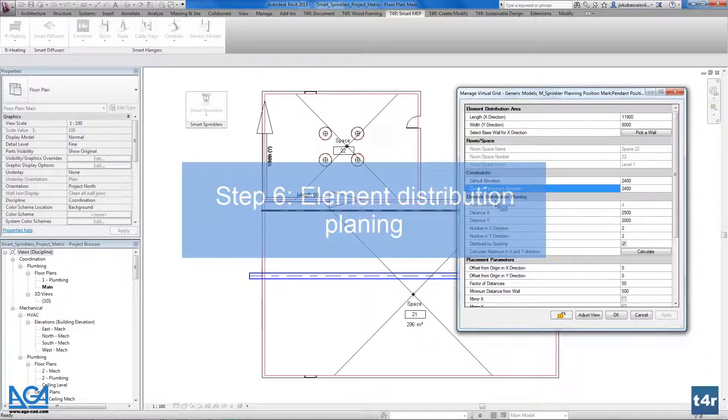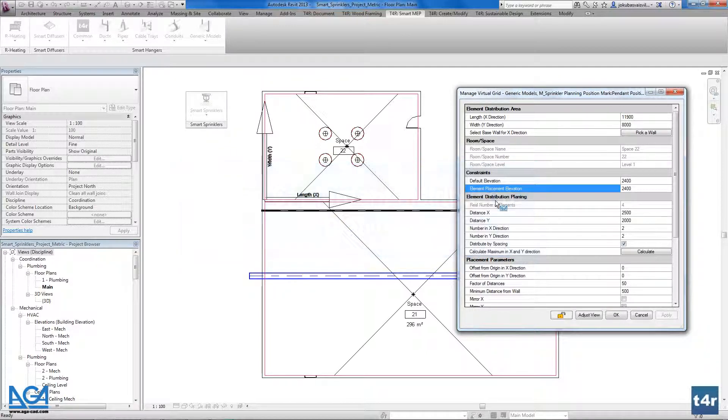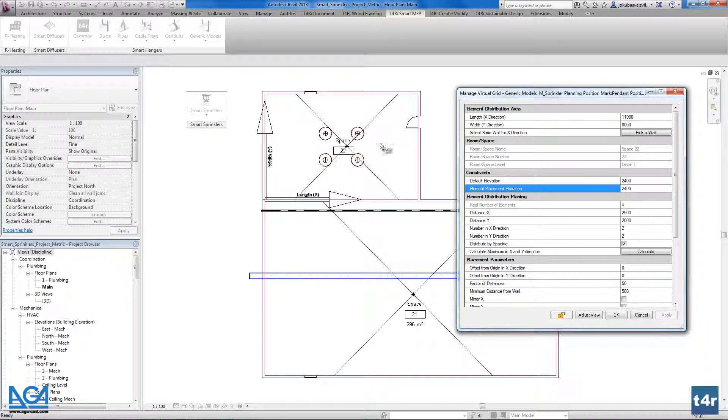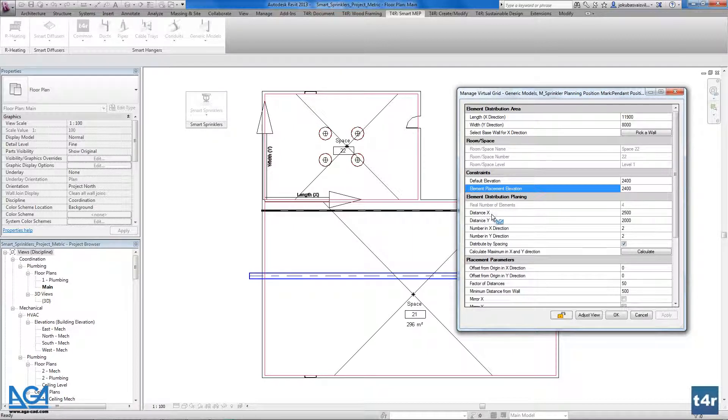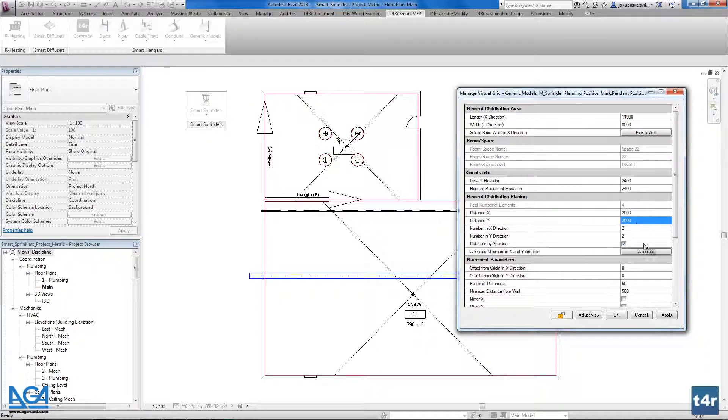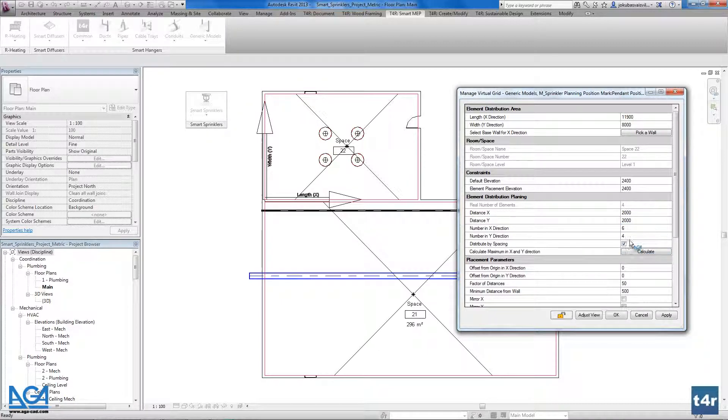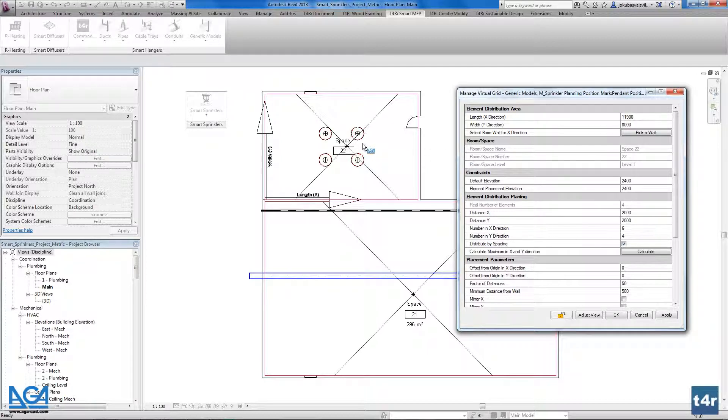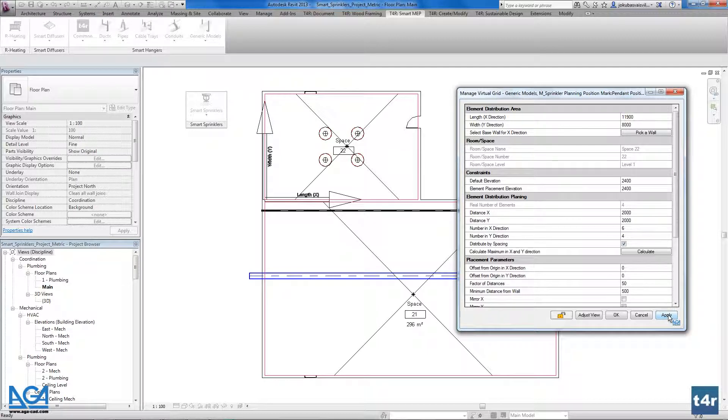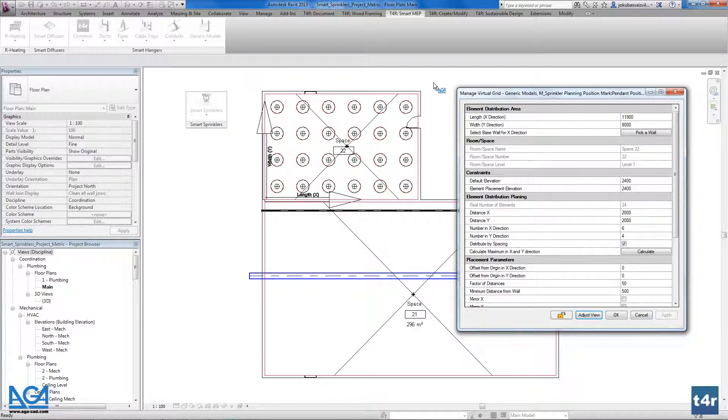Here we have the element distribution planning. The element distribution planning allows us to distribute our elements in a space. For example if we have the distances in X and distances in Y in between our sprinklers. For example we have 2 meters on 2 meters and we could calculate the real number on X and Y directions that will be placed in our space. I will push apply and as you see we have the distribution.